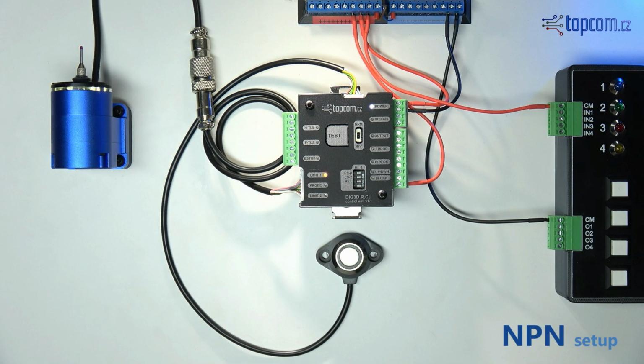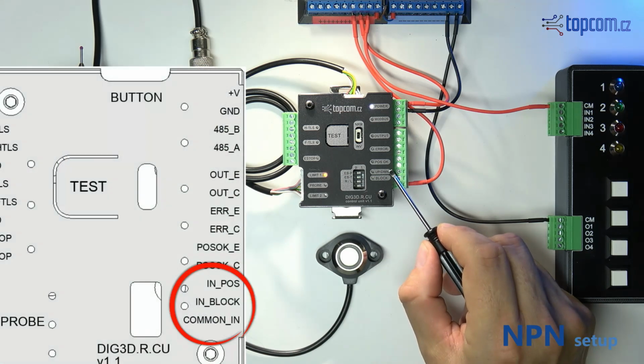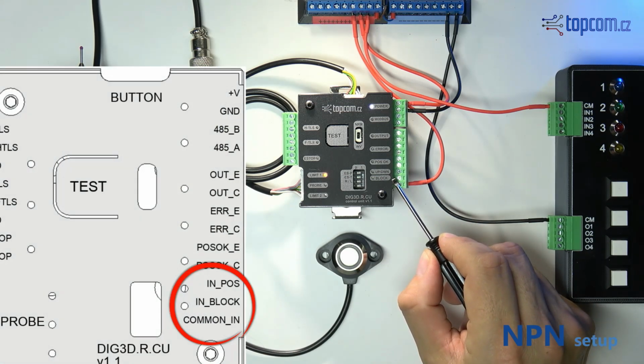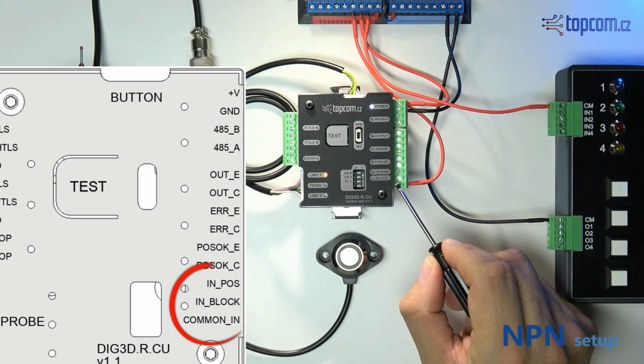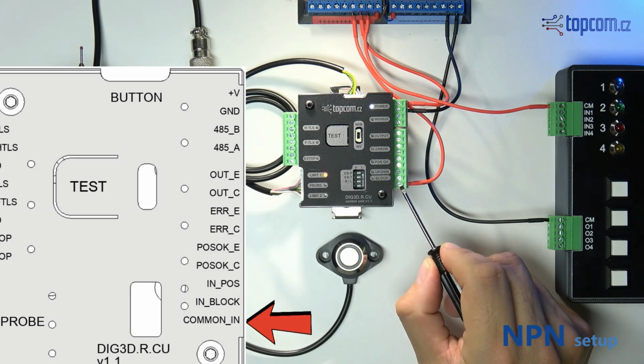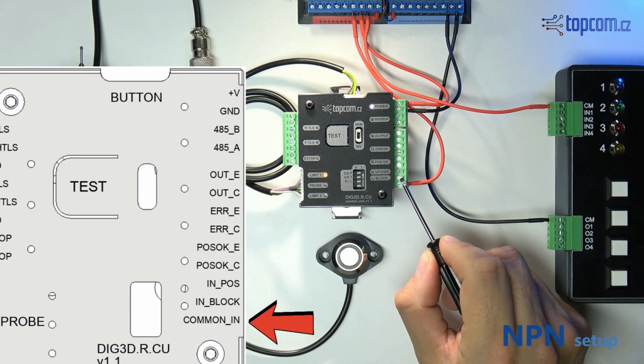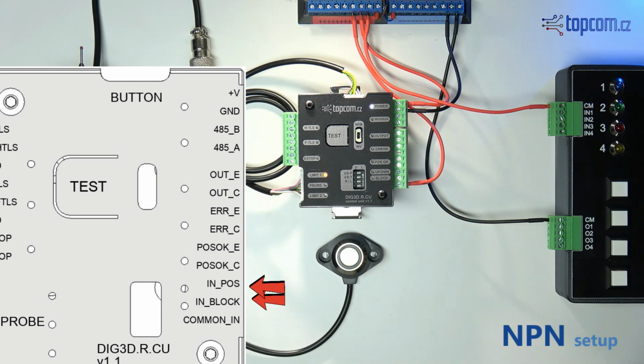The control unit has 2 inputs from the control board, one for setting the probe position and the other for disabling the probe guard function. These inputs share a common line, which is connected to the positive pole in an NPN configuration. The remaining 2 terminals are connected to the control board.